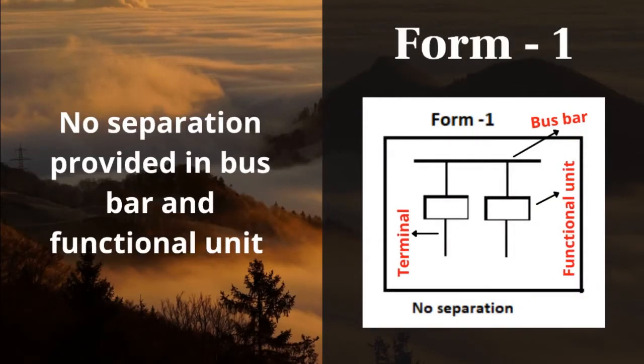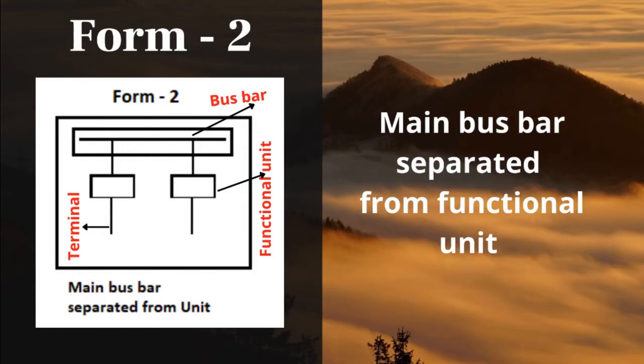Form 1 provides no separation between busbars and functional units. Form 2 has the main busbars separated from the functional unit.